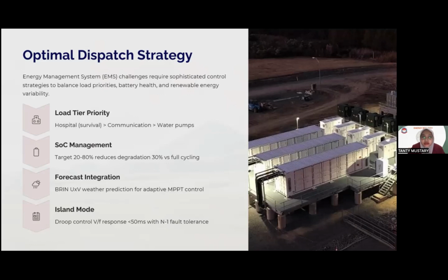Critical load tiering is applied to ensure that hospitals and life support services are supplied first, followed by communication infrastructure and essential water systems. State of charge management is maintained within the optimal range of 20 to 80%, which has been shown to reduce battery degradation by approximately 30% compared to full deep cycling.